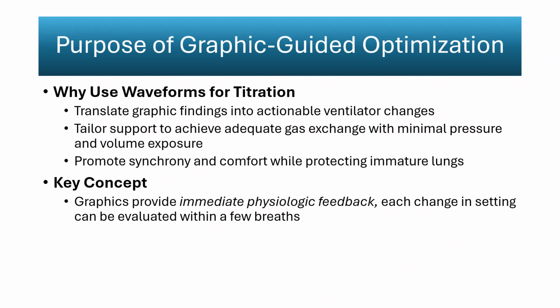Graphic-guided titration allows the clinician to move beyond fixed settings and adjust ventilation based on how the infant's lungs are actually behaving breath to breath. Pressure, flow, and volume patterns reveal whether gas exchange is being supported with an efficient combination of tidal volume, mean airway pressure, and inspiratory timing. Using these signals, support can be fine-tuned to minimize the mechanical load on immature lungs while still achieving adequate ventilation and oxygenation.